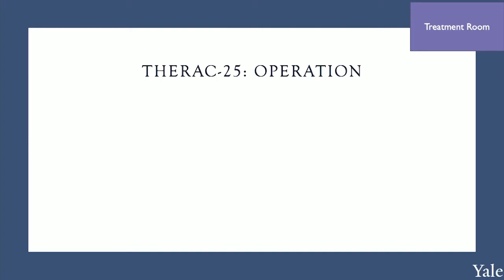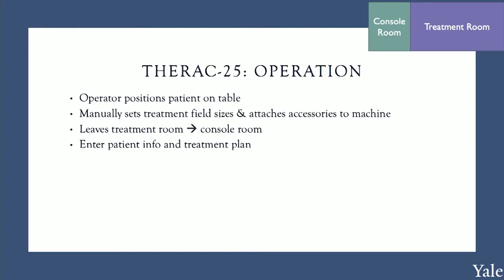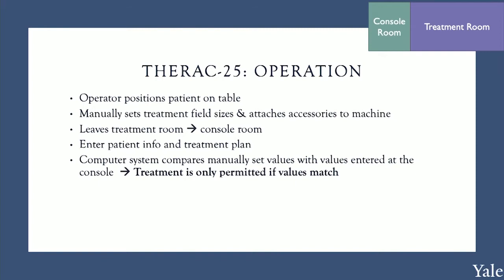So let's walk through an operator's interaction with the software. The operator first positions the patient on the table in the treatment room. He or she manually sets the treatment field sizes and attaches the necessary accessories to the machine. The operator then leaves the room and controls everything from a console room. The patient's info and treatment plan are entered into the software system, and the computer checks to make sure the manually set values match the values typed into the console. If the values match, treatment begins. Operators then began complaining that it was redundant and time-consuming to re-enter the data into the console system, so the Atomic Energy of Canada Limited, or AECL, modified the software to copy treatment data from the manually set values.